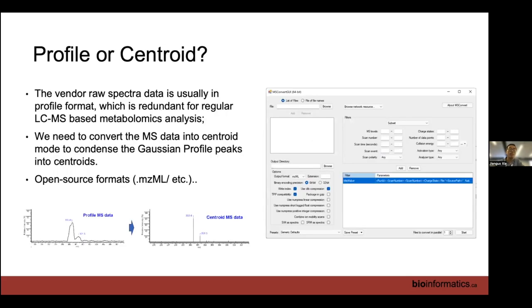Within the same machine and same matrix running on the same day, results should be very stable. Nowadays machines are quite robust, and with internal standards you can achieve spectral stability. If not, you need to calibrate your machine. The raw spectra generated from the machine is called a profile, and we need to convert it to centroid mode — condensing the Gaussian profile into a centroid.